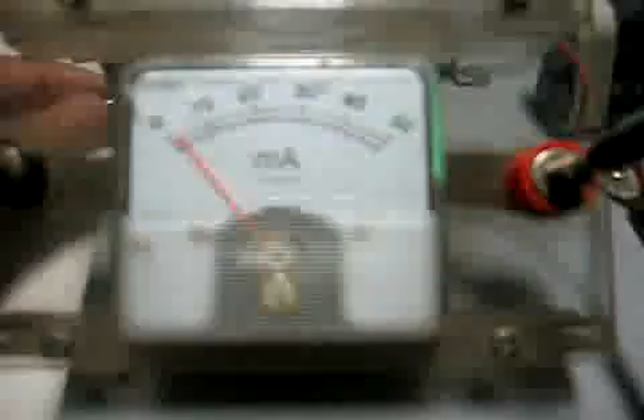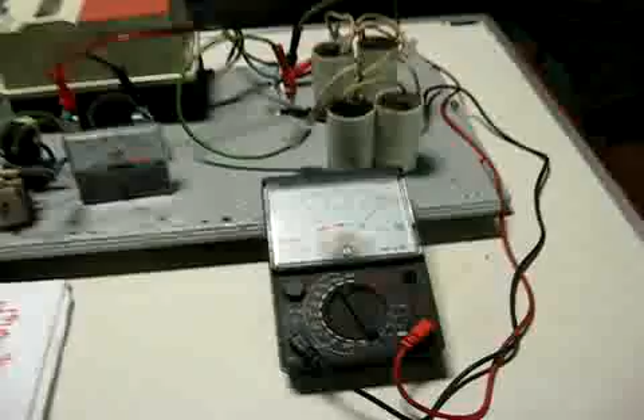And again, now the meter, now it's 1000, and this is slowly going to go down because of the leakage resistance. But that's 1000 volts. So one more time, discharge the capacitor.